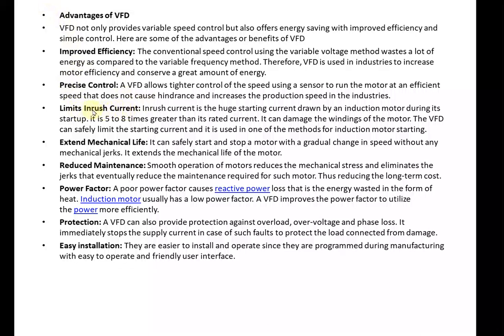The VFD also limits inrush current. The inrush current — the huge starting current drawn by an induction motor during startup — is five to eight times greater than its rated current, and can damage the motor windings. The VFD can safely limit this starting current and is used as one of the methods of induction motor starting. Another advantage is that it extends mechanical life by safely starting and stopping the induction motor with a gradual change in speed, without any mechanical jerks.